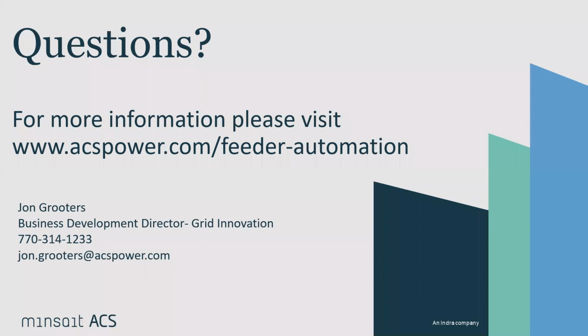Certainly, a more deterministic point-to-multipoint network is probably going to give the best overall performance and speed, although the more modern mesh networks that are being built with quality of service and some deterministic capability to support automation certainly have the capability to support this system.